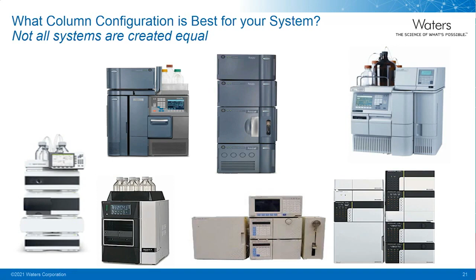Now, it's very critical to understand the LC system, specifically what impact it contributes to the separation. So let's take a closer look at what makes the LC systems different. Instrument dispersion is really at the key of it. Every LC system contributes to the broadening of the analyte band. It's an individual system dispersion value that can be measured to identify exactly how much volume the system is contributing. It's important to classify the LC system by this value. Typically, HPLC systems have high dispersion values, where UHPLC have very low dispersion values. Selecting analytical columns that best match these values is critical to achieving maximum chromatographic performance.